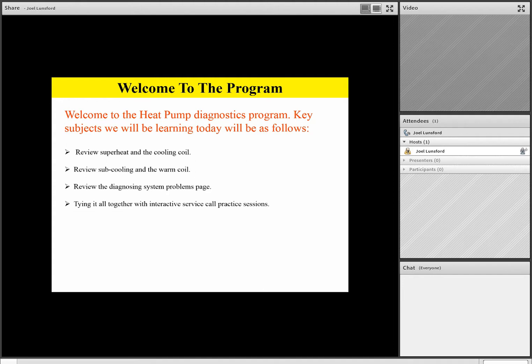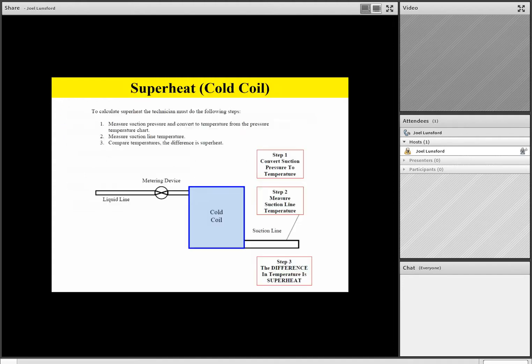So again, reviewing superheat and the cold coil. To find superheat, we're going to convert our suction pressure to temperature. We'll then measure the suction line temperature and find the difference, and the difference will be our superheat level. Now remember, team, on superheat, if the superheat is high, the cold coil is starved. If the superheat is low, the cold coil is flooded.